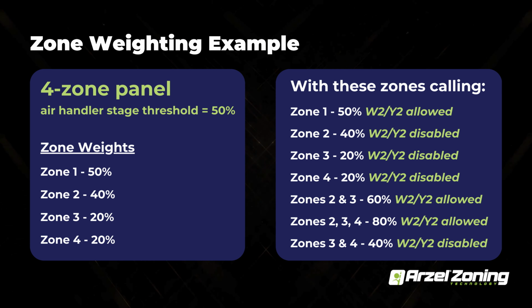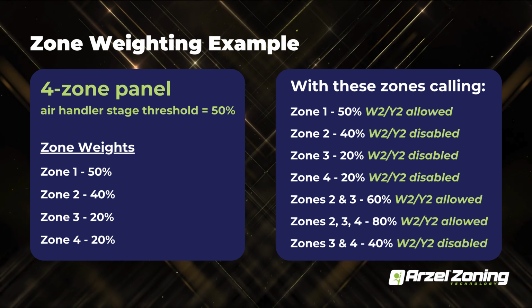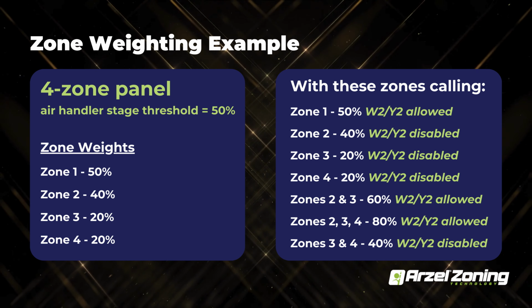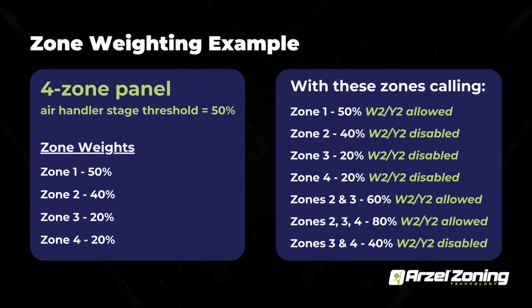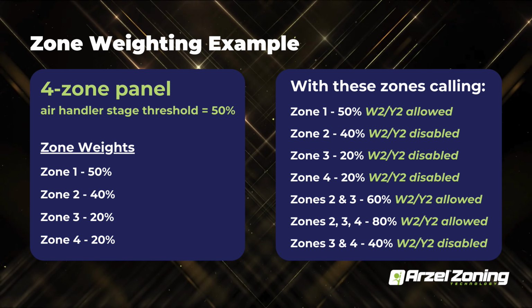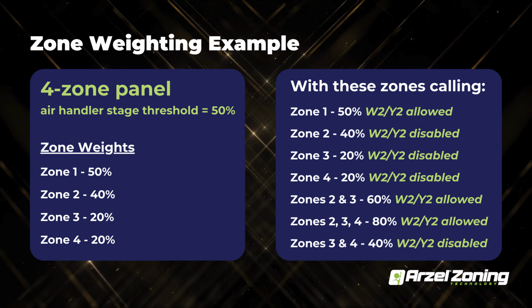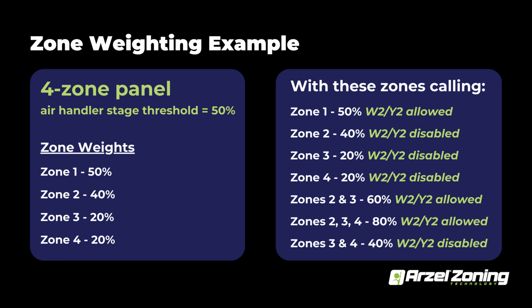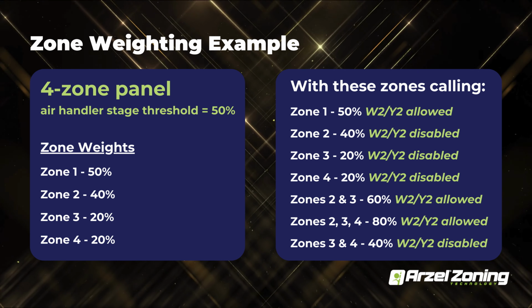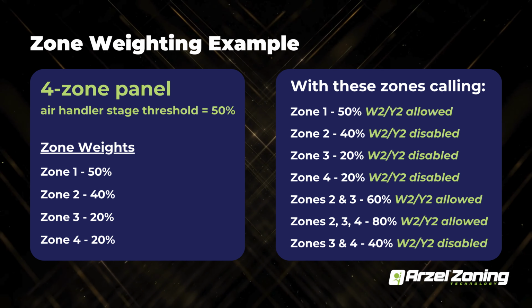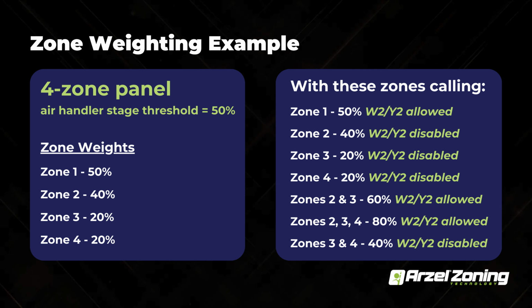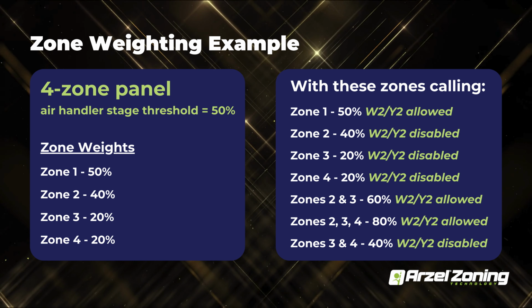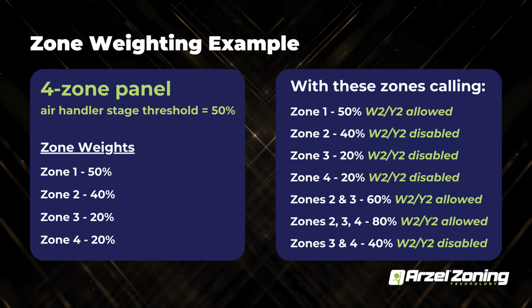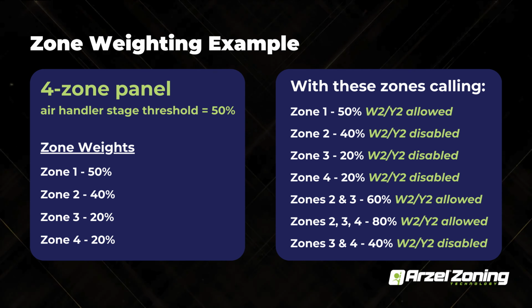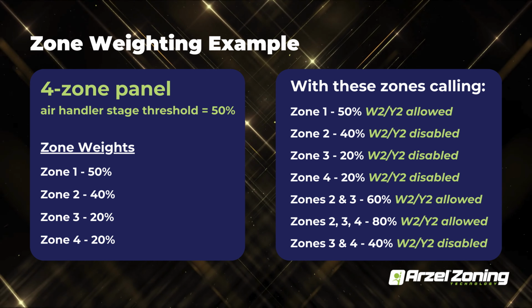So you've got a 4-zone panel, air handler stage threshold of 50%. Your zone 1 is set to 50. That's going to allow for second stage output. When you're going into zone 2 at 40%, second stage is going to be disabled because we cannot hit that air handler stage threshold. We're less than that. When you get into zone 3, 20%, we're still under 50. We cannot go into second stage.